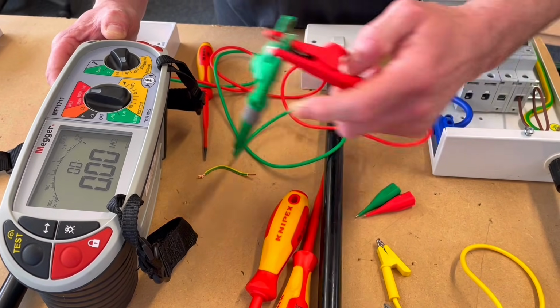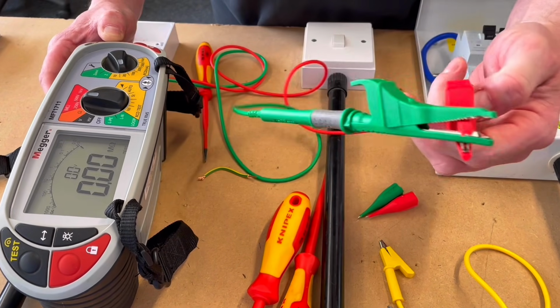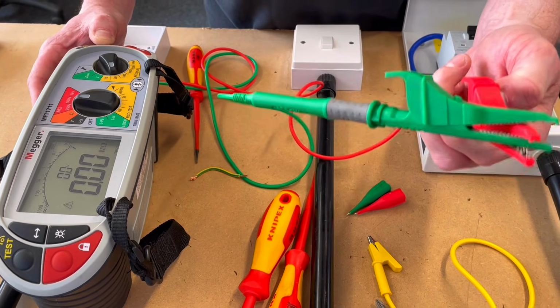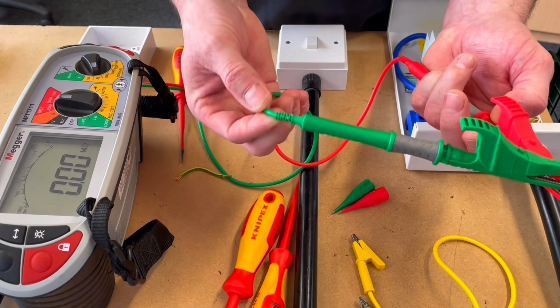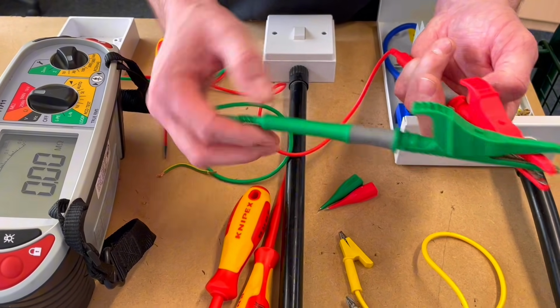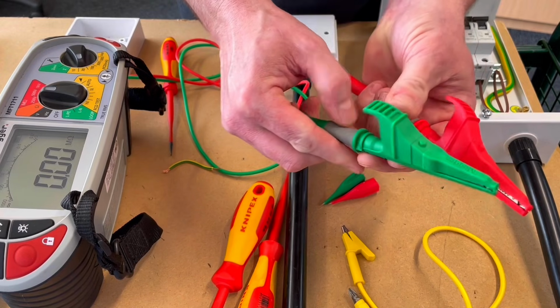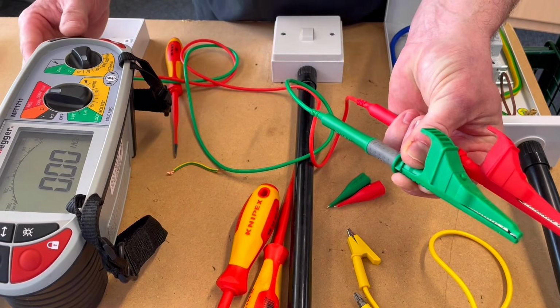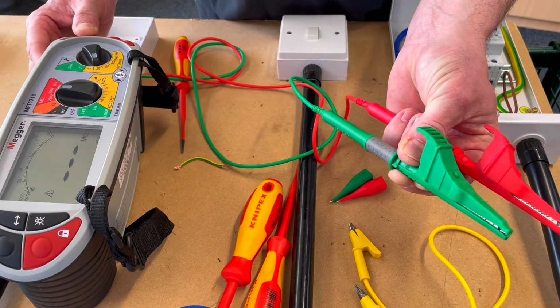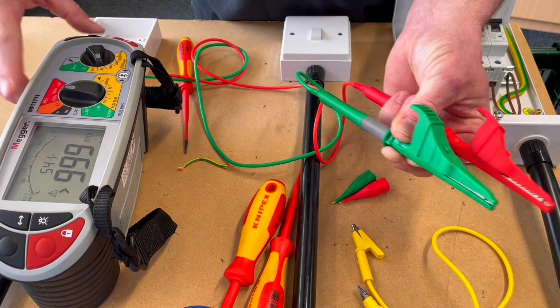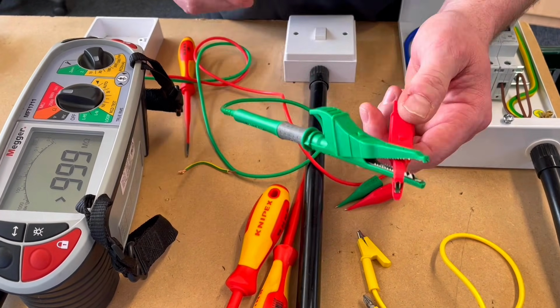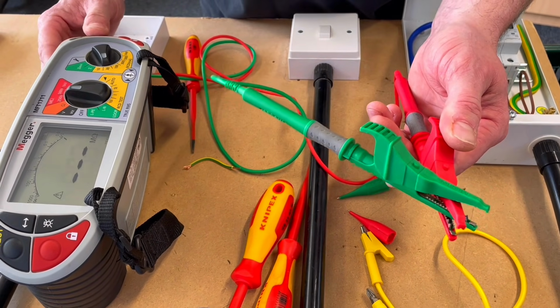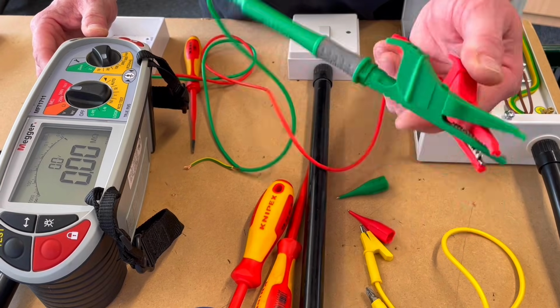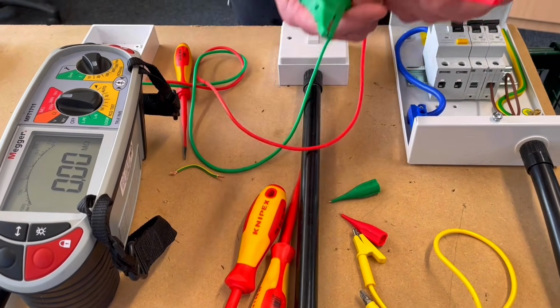And as they're joined together, I've got 0, 0, 0, in other words, a dead short, meaning the leads are in good condition. If these leads were snapped, and again, I've done a little video on them, and they tend to snap around here, what you end up with is the equivalent of it being broken. If I press and hold the tester again, you get a reading greater than the machine can read. So if we're going to short them together to prove that they're not broken, we expect to get 0 or a dead short for that reading. So our leads are good and we're ready to test with these.